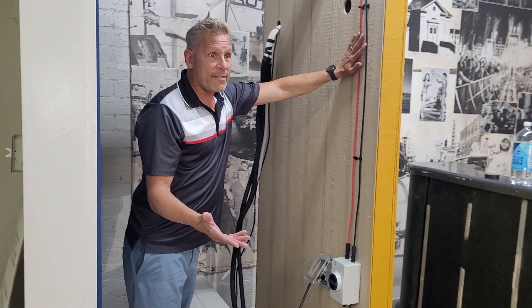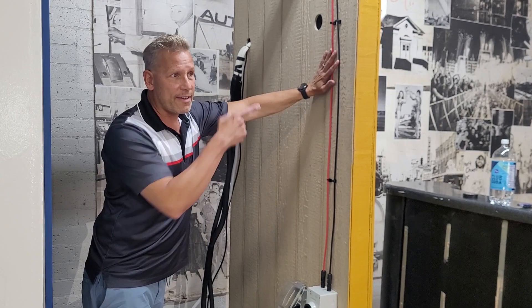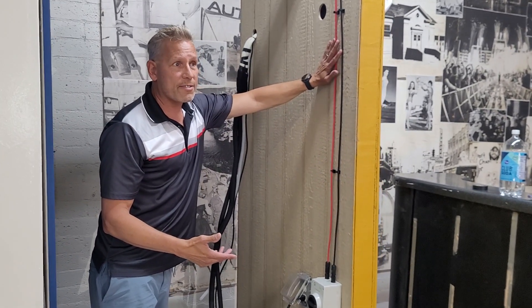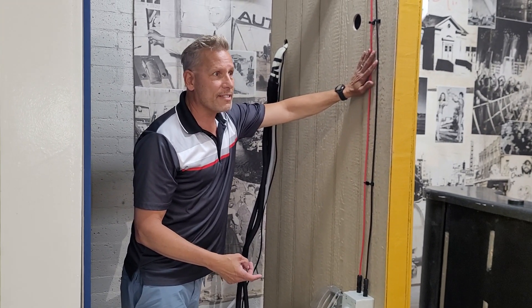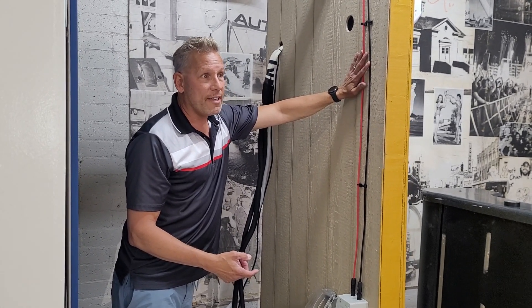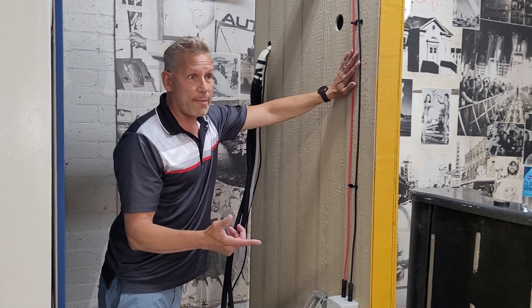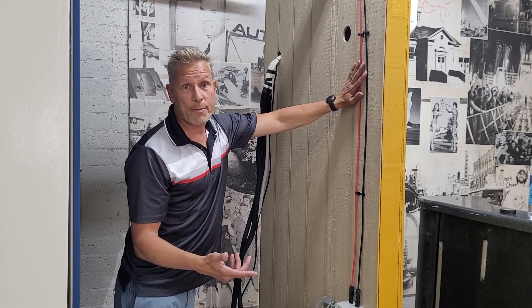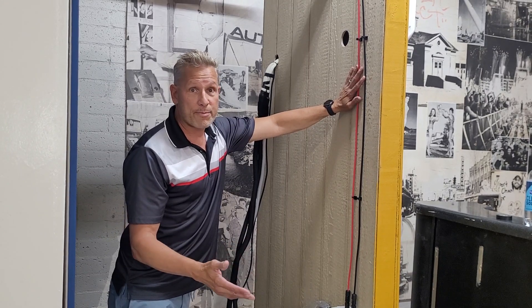Here in Las Vegas, the panels we have up there are 1520 watts on our one-ton unit, and in July and August when it's 110 degrees here, they're probably only producing maybe a thousand to 1100 watts. And in the summertime you get double jeopardy because the compressor needs a lot more power in the heat of the summer than it does in the spring or fall.